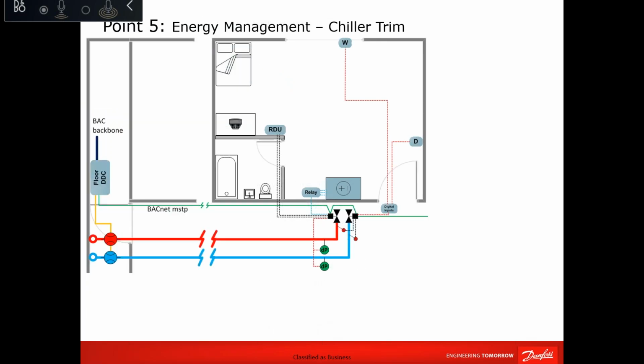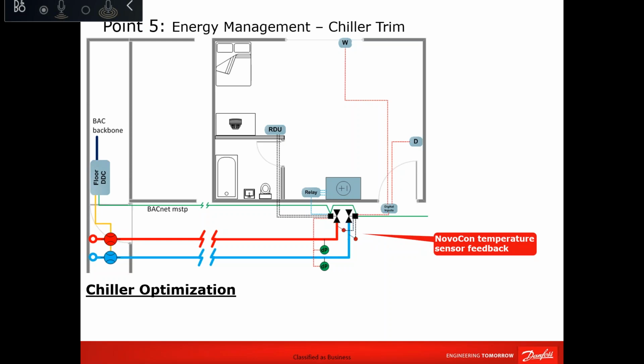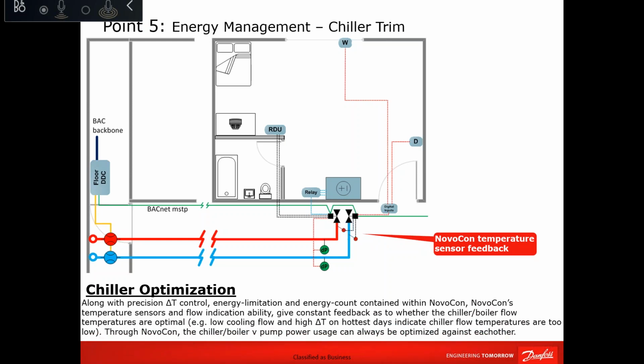So energy management, here is another feature that can be useful, since the BMS is seeing everything. How is this done, and how can you optimize the chiller? We said that you have the temperature sensor on the Novocon, and then with the delta T control, energy limitation and energy count, which are all features inside the Novocon, you can find out up to which temperature you are not affecting the comfort level. Let's say you are achieving the comfort level with 5.5 degrees supply chilled water. Now you are increasing from the chiller to 6.5 because you have the data on that area.